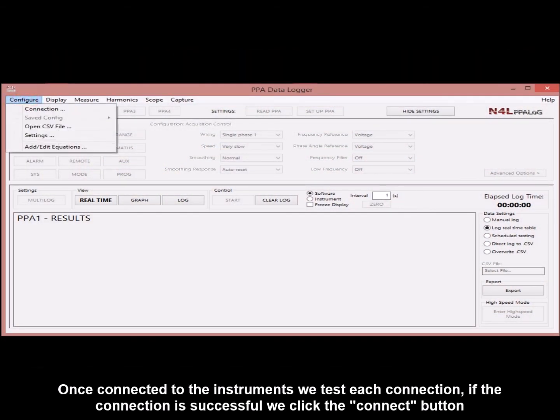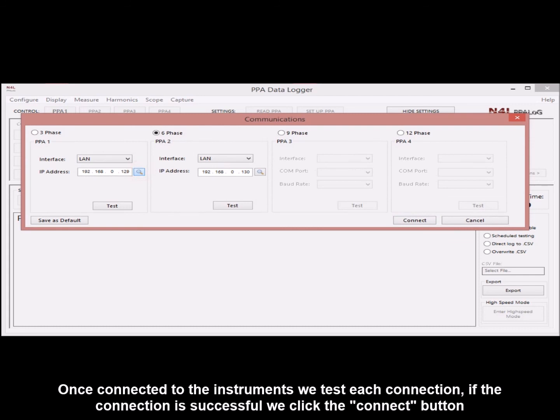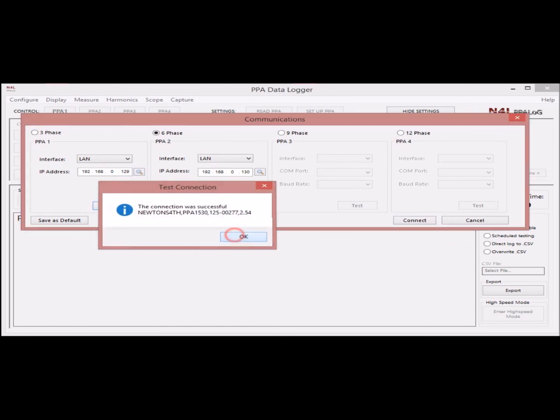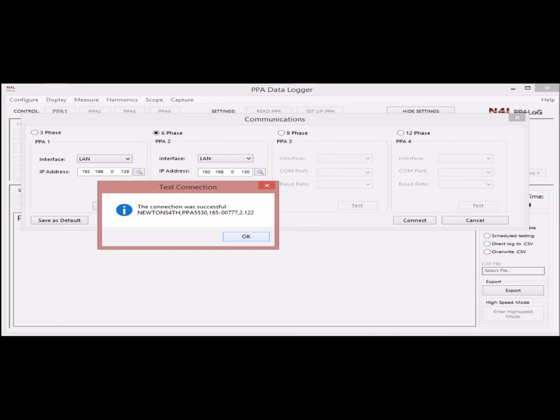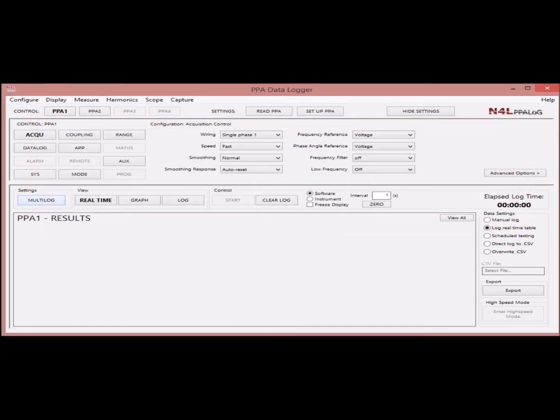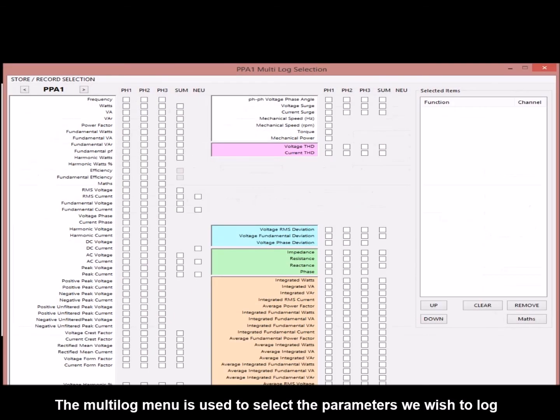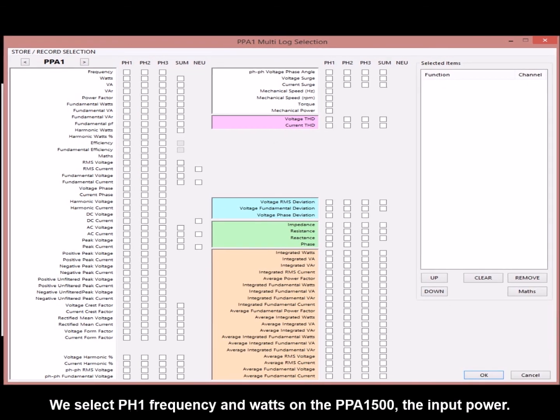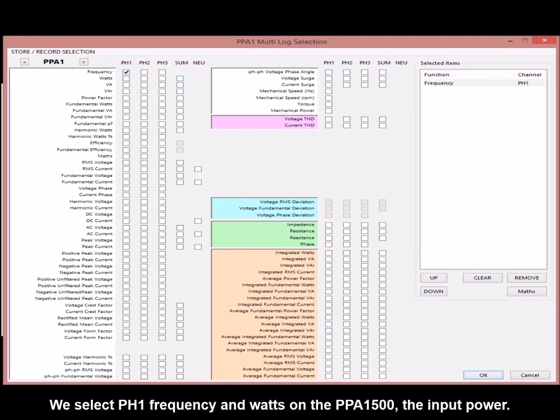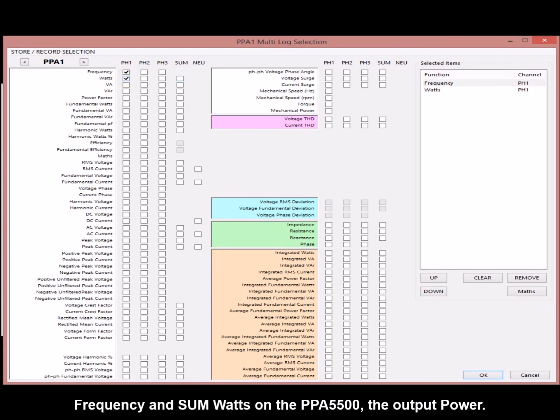Once connected to the instruments, we test each connection. If the connection is successful, we click the connect button. The multi-log menu is used to select the parameters we wish to log. We select phase 1 frequency and watts on the PPA1500, the input power, frequency and SUM watts on the PPA5500, the output power.